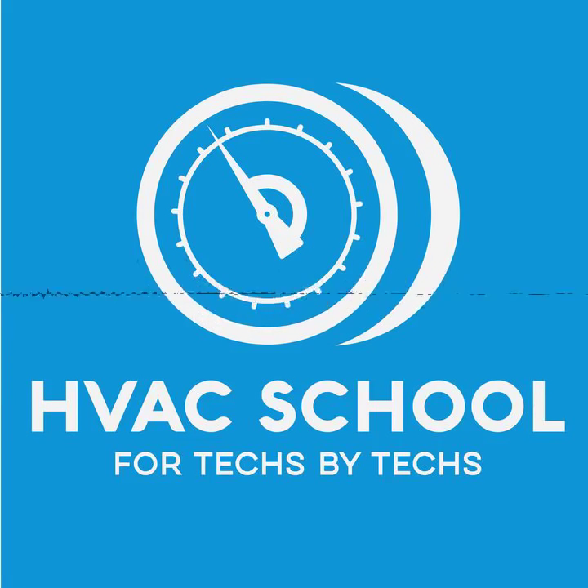Well, first off, something we have to understand when we're using a pressure control is pressure controls are never 100% accurate. They are actually very inaccurate devices. Oftentimes, they will have a number on a little readout or a dial on the control that says 20 PSI, 30 PSI, or sometimes they're a differential control where it'll say cut in, cut out minus differential. Those numbers are never set in stone accurate. The only way to know if it's accurate is to field calibrate the control. Typically the easiest way is to use some nitrogen, apply so much pressure to the control and write down when it's set at 20 PSI, where does it actually turn on and off, and record those. So then that way you have an idea of how accurate the control is.